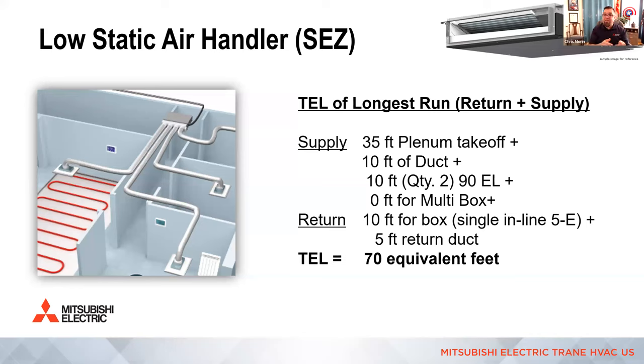And then in this example, I had 10 feet of round branch duct. And in that branch duct were 2 long sweep 90s. I apologize, 5 feet each for long sweep 90s, times 2 is 10 in this example. And then because I have an AirTech diffuser, like somebody asked about, there was no additional feet on the supply for that boot. But if you're going to go into a floor or a ceiling and you have a register boot, you need to actually account for that boot as well. And those can range anywhere from 5 if they're straight to as high as 50 if it's a right angle boot that goes into a floor.